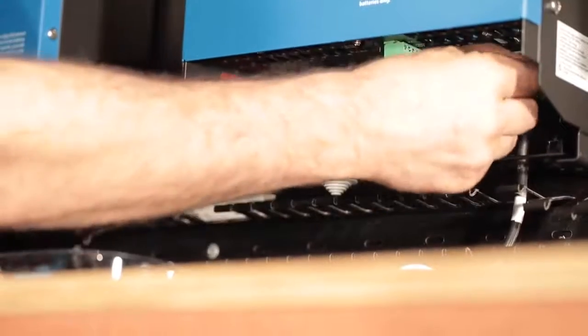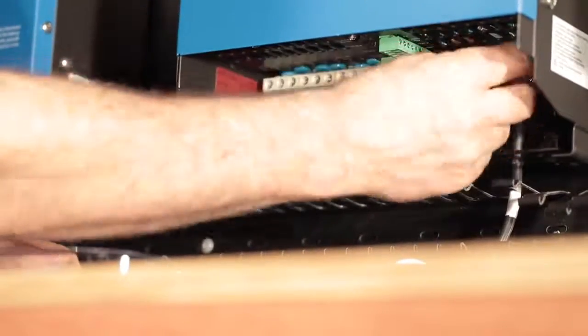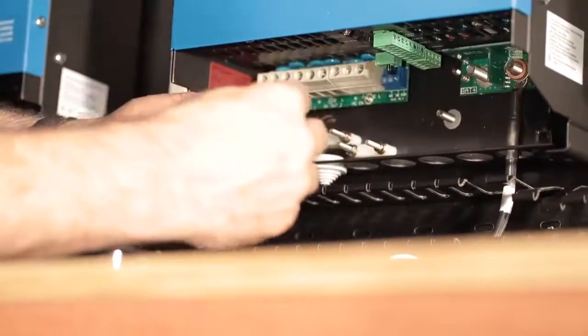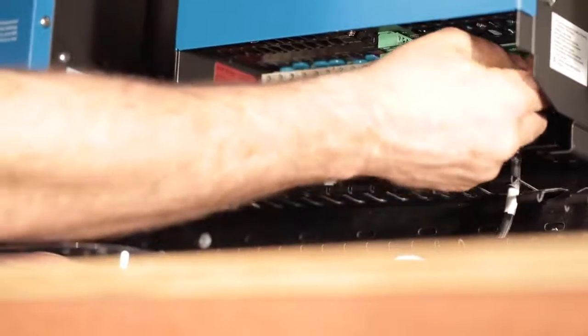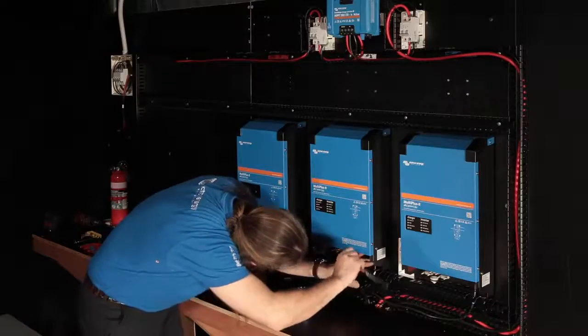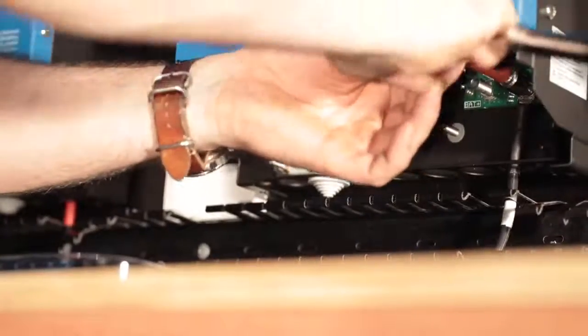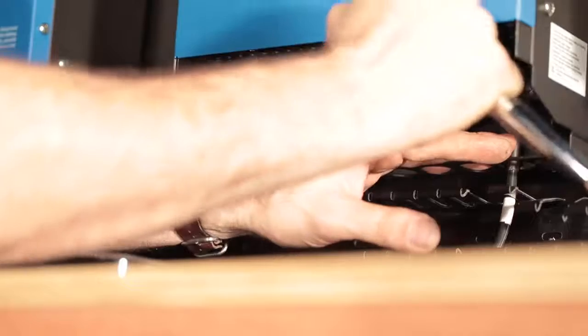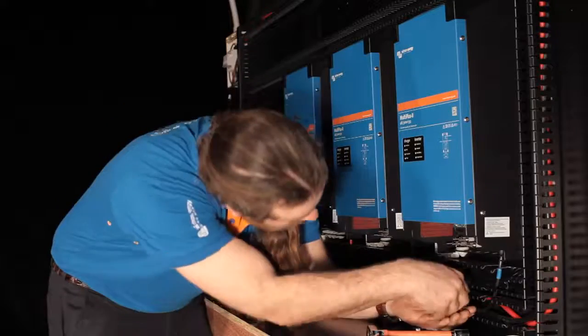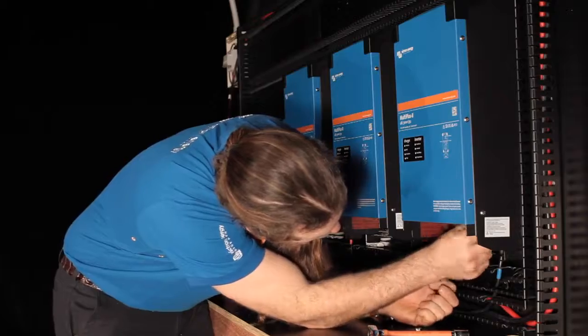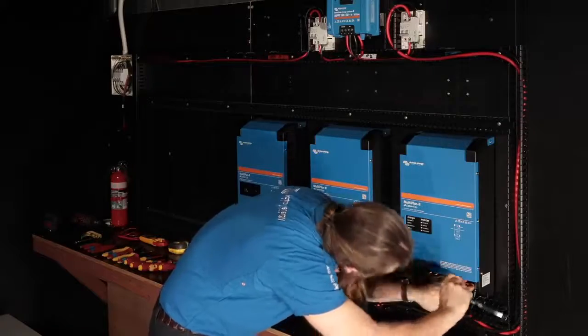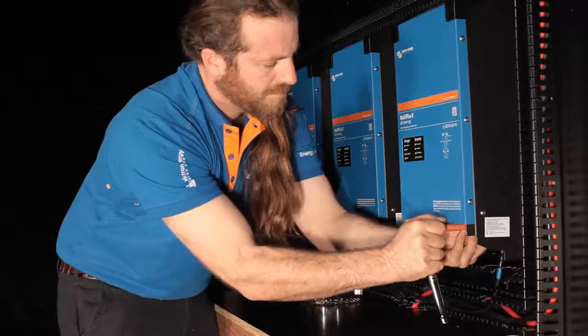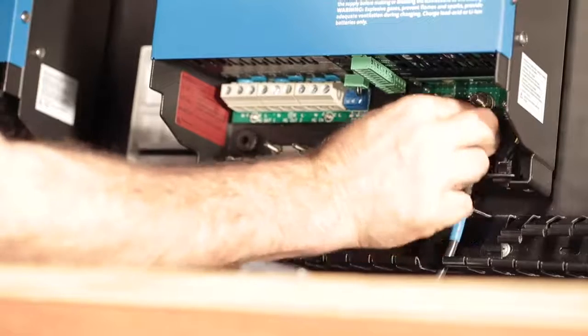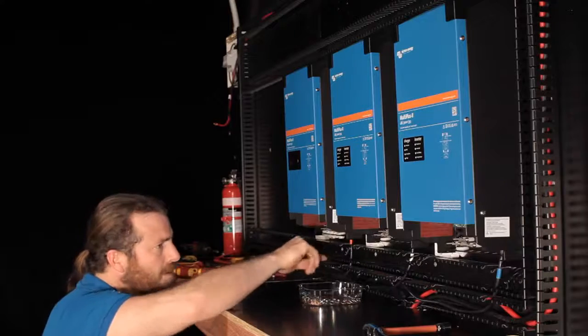Once you've got the lugged cables on the M8 nuts and bolts, attach the flat washer and then the spring washer and then finally the nut. Tighten it up with your wrench to the rated torque in the manual. Take your time making these important connections and definitely double check them all to make sure they're all secure. You also want to double check your polarity.